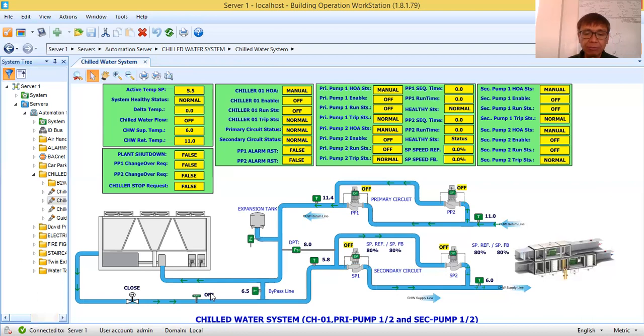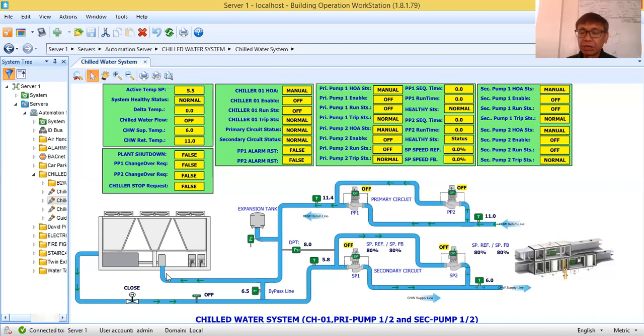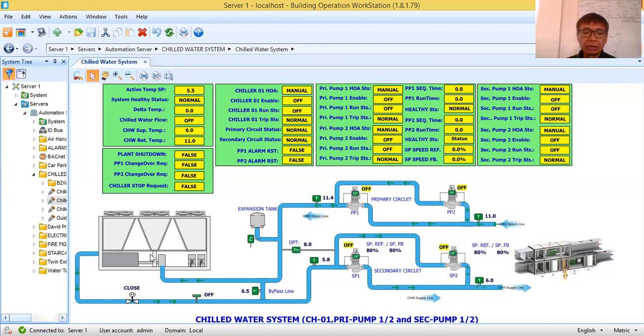I have a flow switch that will try to detect if there is flow in the evaporator or cooler. If there is no flow, this chiller will try to shut down itself to prevent freezing of chilled water in the cooler.